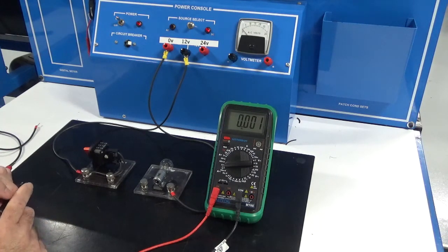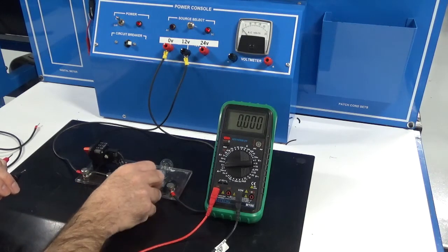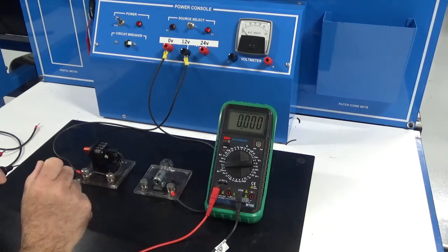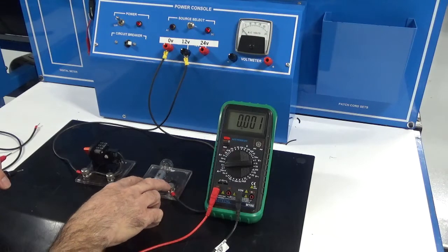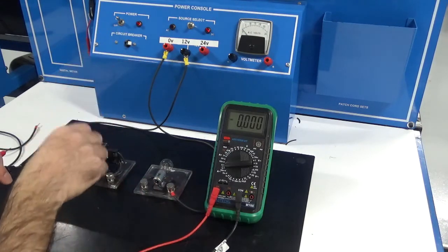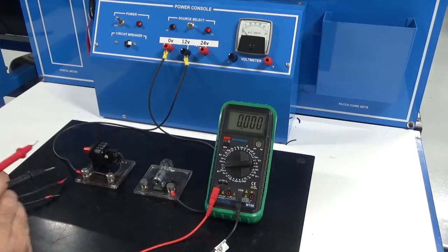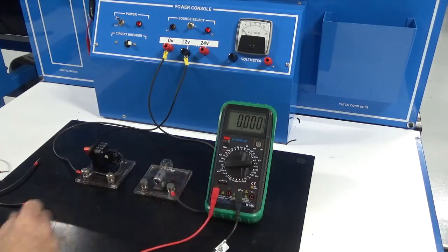For resistance readings, we have to isolate the component we want to read, so we have to take at least one side of one lead off of that component. So when we read the resistance across this component, we're not reading back through the power supply and other parts of the circuit. And then for a current read, we have to remove a conductor and replace that conductor with a meter set up to read current. So that's what we have.